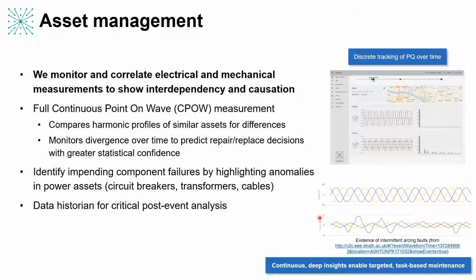We have patents around that, on how we capture the time in a central location and shift everything. At a central location, we can gather in, say, 50 measurements, all of the voltage at different points in a system, and we've got every single measurement sample time correlated. From that, we can go into the real detail on the system and look at oscillations, transients, and more importantly, the sample-by-sample correlation between what's happening at different points in that system. That's information you can't get from synchrophasor data, because for reasons of data efficiency it is traditionally thrown away. But there's a huge amount of insight and value there if you can capture it. The question is, can you capture it cost effectively? And that's exactly what we're setting out to do.